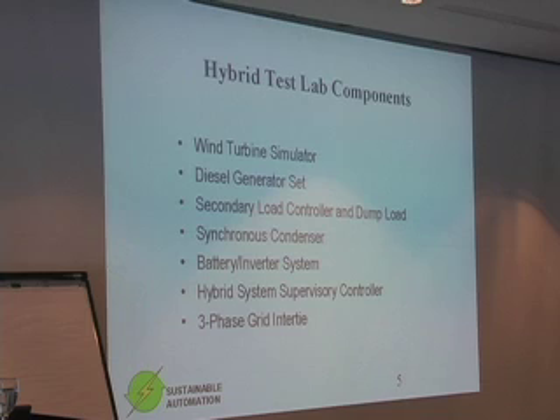We have a generator set, a secondary load controller, synchronous condenser, recently installed a battery inverter system. And although most of our applications are off-grid, it's useful to be able to interconnect with the grid, both for testing individual components, but also to, on occasion, simulate systems that actually would be grid-tied, which might be the case in, say, an industrial system that might want the option to disconnect from the grid at times.